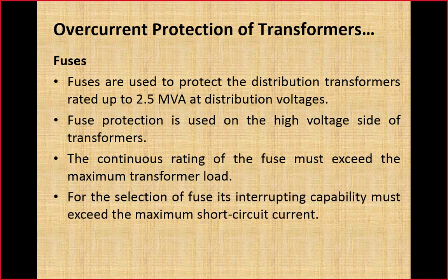Second, the interrupting capability, the maximum current that a fuse can interrupt. The interrupting capability of the fuse should be greater than the maximum possible fault current for which this fuse has to operate. So these are the two conditions for the selection of fuse.